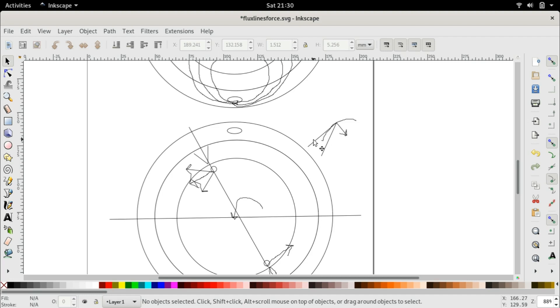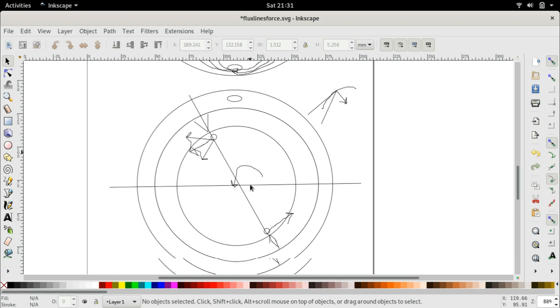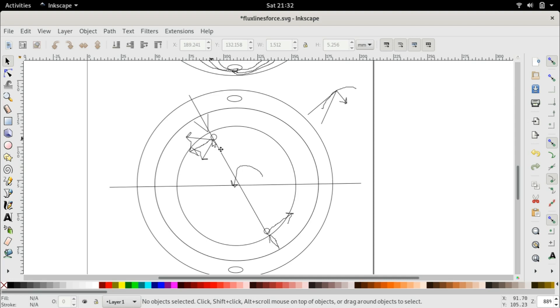The component of force along the tangent is the usual component that results in rotation, producing rotational torque. The other component of force along the radius does not produce rotational torque — instead, it produces vibrations. Because of these non-idealities, the components of force along the radius result in vibrations of the rotor. The rotor not only rotates but also vibrates. Any motor will face these kinds of vibrations because you always have these non-idealities. Around 1 to 2% of the magnetic lines of force will not follow the ideal path of least reluctance, and because of this, they produce radial force components.